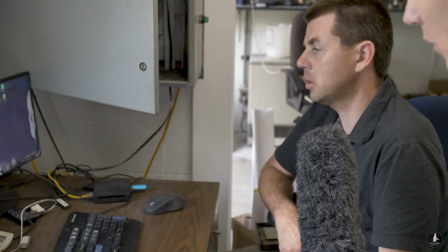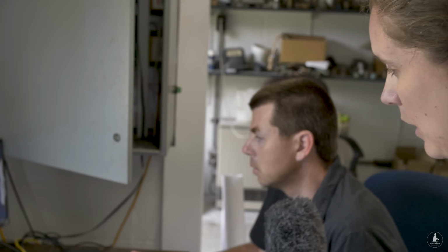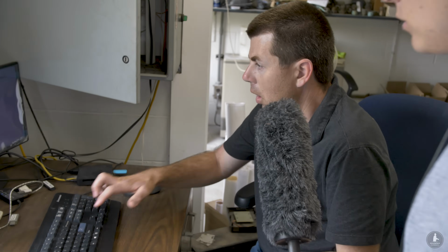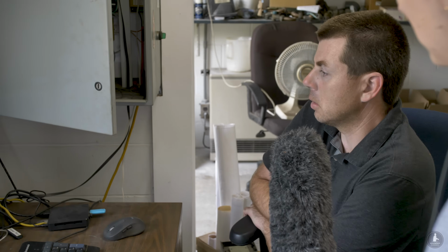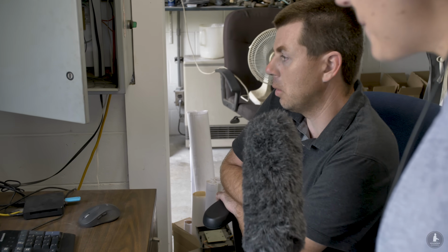See the chlorine change? Yep, so you can have more chlorine because you've increased. So I can change that just by sitting here. And why would you want to change it? Because of flow. It should all be flow paced. It's a term we use in this business.